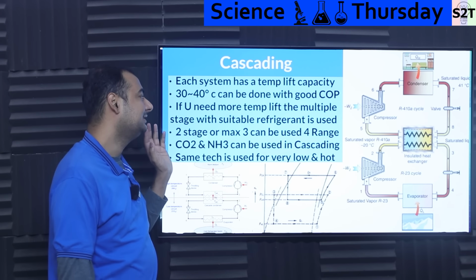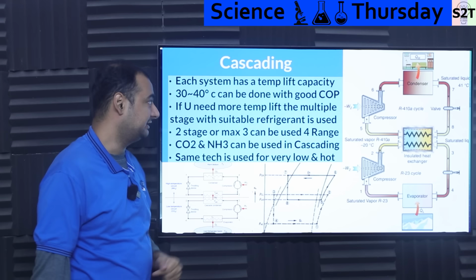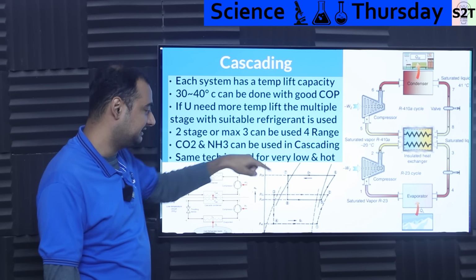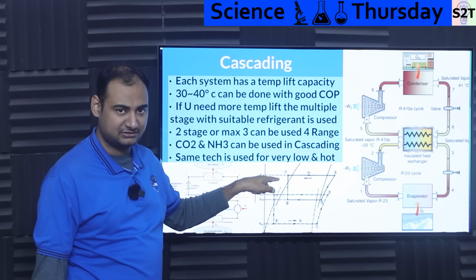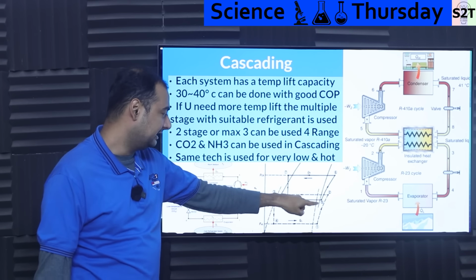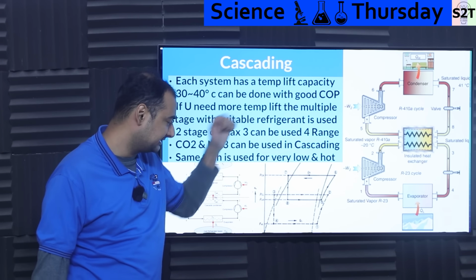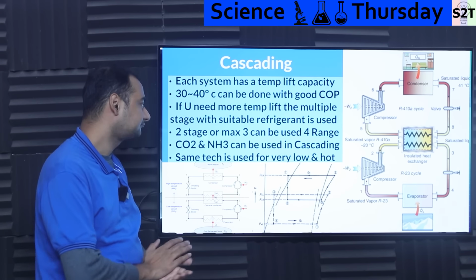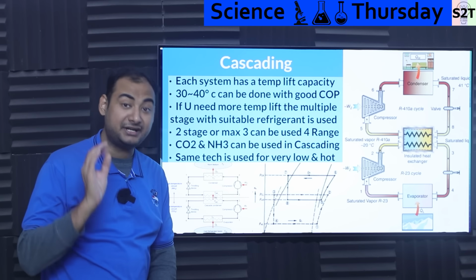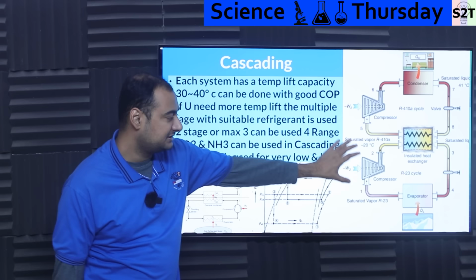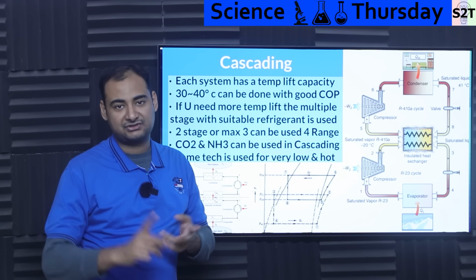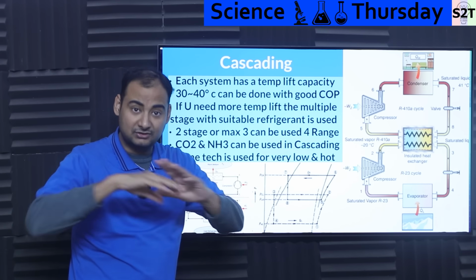So at that point, you link multiple cycles, what we call cascading refrigeration. Basically you have one refrigerant taking care of one section and one temperature lift, and a second refrigerant creating the second temperature lift. This way you get the luxury of fine-tuning a system, basically figuring out what is the best refrigerant, best compressor, best everything for this lift.